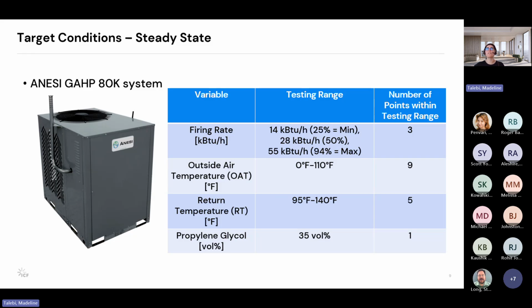And I'll probably touch on that a little bit more later in the presentation. And then looking at the outside air temperature, a range of 0 to 110 degrees Fahrenheit, so 9 points within that range. The return temperature, 95 to 140, so 5 points within that range. And then the propylene glycol volume percentage was kept constant at 35. And the steady state testing was mostly used to set the baseline that we can use for the part load testing.